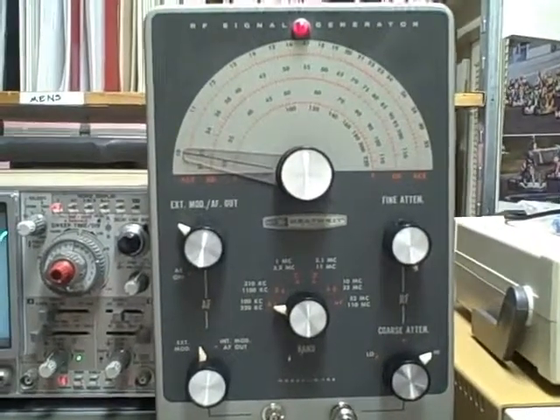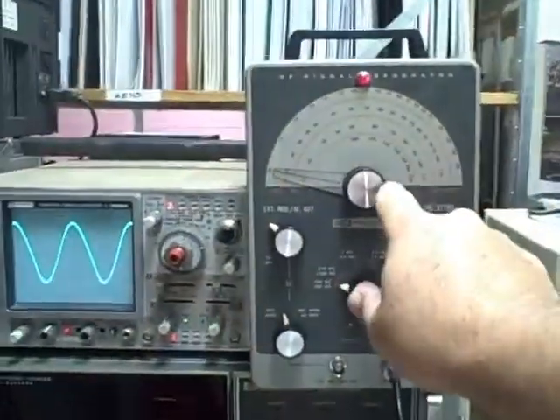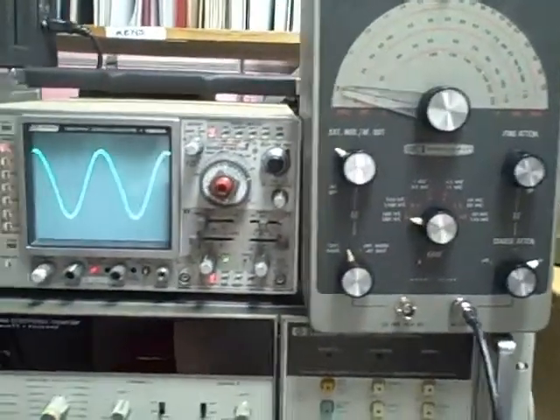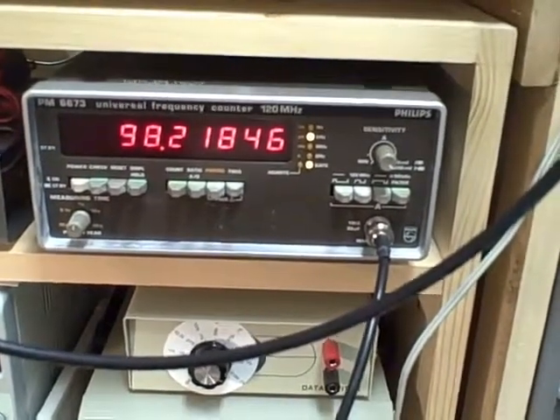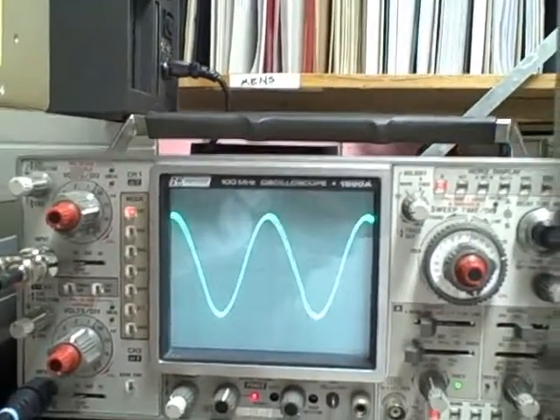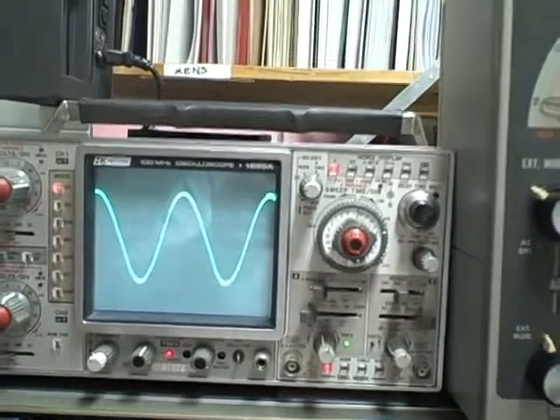Right now I'm on Band A, which covers 100 kilocycles to 320 kilocycles. I've got it dialed down to the 10 mark, which represents 100 kilocycles. I've got a frequency counter connected, and we can see that 100 kilocycles is showing up as 98.2 kilocycles — well within the 2% we're talking about. On the oscilloscope we get an idea of what the waveform looks like.